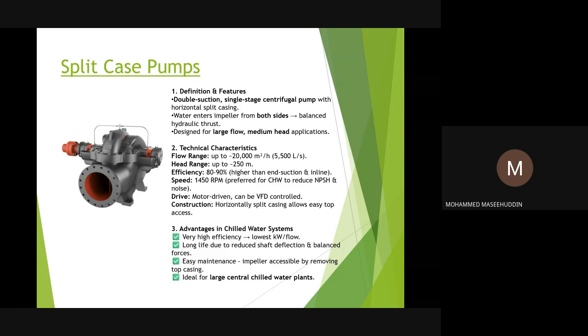These pumps also have higher efficiency compared to end suction pumps, because in end suction we can typically have about 70-75% efficiency based on the type of pump selected. But in the case of split case pumps, we can reach efficiencies of maybe up to 90% sometimes, depending on the duty conditions of the pumps. It runs at 1450 RPM, with a 4-pole motor, which is preferred for chilled water to reduce net positive suction head and noise.